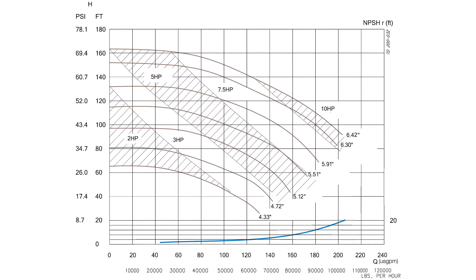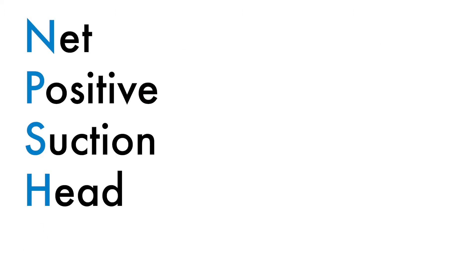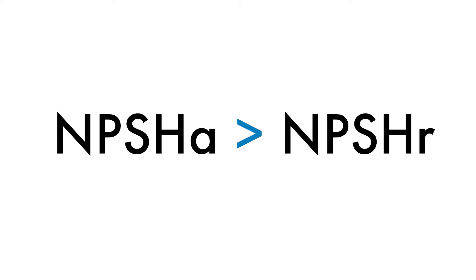The other side of the equation is NPSHA, with an A standing for Available. NPSHA is determined by the process piping. You always want NPSHA to be greater than NPSHR.